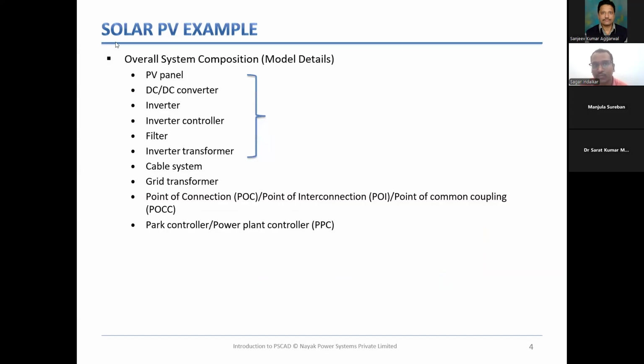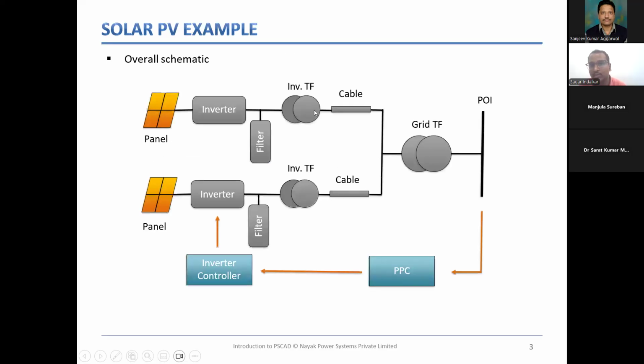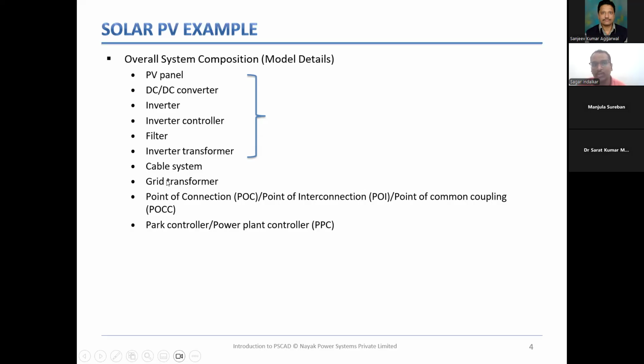So overall plant will consist of your PV panel, your DC converter. This is basically your boost converter to obtain maximum power point tracking. Then you have your DC to AC converter. Then along with this converter, you will have your controller that will control the output of the inverter. You'll have those filters, harmonic filters. Then you'll have your inverter transformer. This one inverter transformer. Then you have your collector system. You'll have your main transformer or grid transformer, and then you will have your point of interconnection. And ultimately, all these things will be controlled by one supervisory device. It is called a power plant controller (PPC).